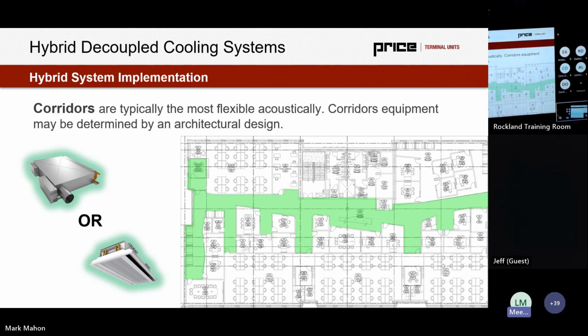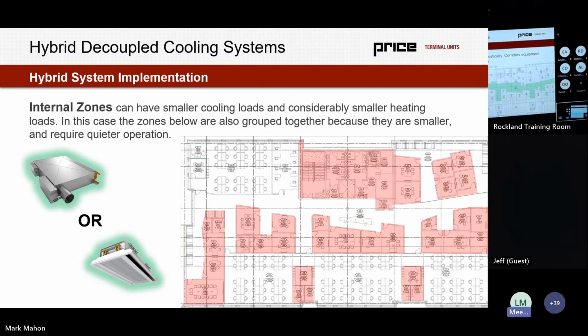And that's because we could get one big piece of equipment with a lot of ductwork that could potentially be operating at a higher acoustical set point. And since it's a corridor, we could just serve a lot of it and really consolidate equipment. That's rationale potentially. Now, I would say this is kind of a toss-up. And I said to the engineer at the time, go either way. It depends on what you'd like. I would defer to the architect in this particular vision for the building, especially with Google. The architect tends to drive the project, so that was a consideration too.